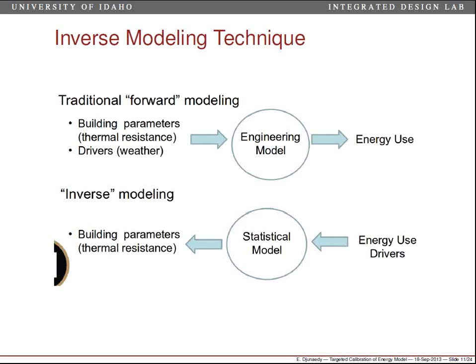Typically the inverse modeling technique isn't used in conjunction with an energy model, but separately as a way to quantify savings. This is the area the measurement and verification project we do for Idaho Power comes from — we want to quantify savings. Idaho Power has paid an incentive for this EEM, so we go to the building, measure, and use this method to quantify the savings — so many kilowatt hours per year.